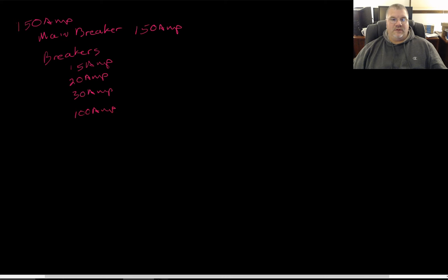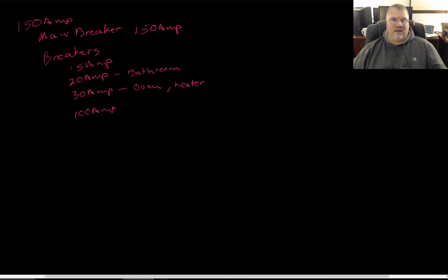Your breaker panel — also called a load center, main panel, or breaker panel — used to use screw-in fuses; some places still do. Breakers are typically 15-amp or 20-amp; you'll also have 30-amp breakers typically for ovens or electric heaters. I prefer using 20-amp throughout the house rather than 15-amp — it's only an extra $2–$3 for the breaker and $6–$10 for a roll of 12/2 wire. 15-amp breakers are typically used for lighting and outlets.